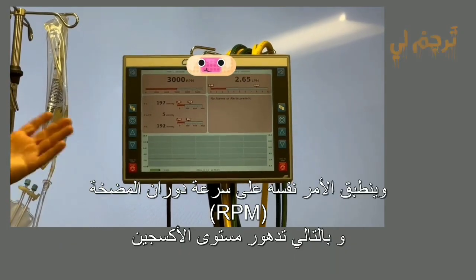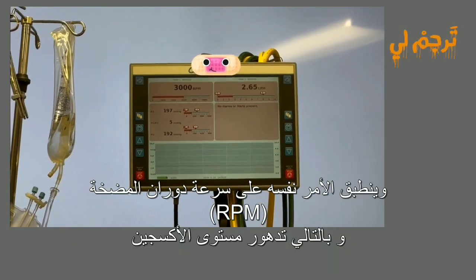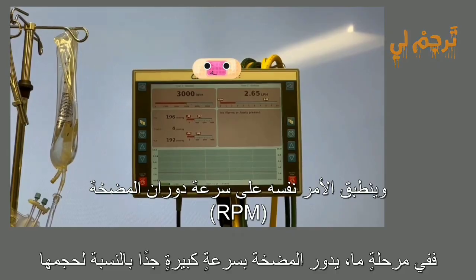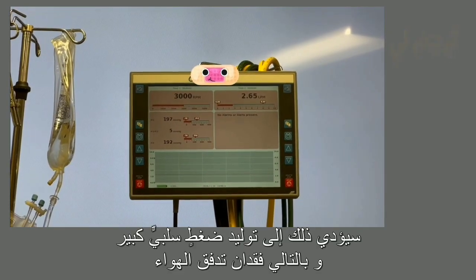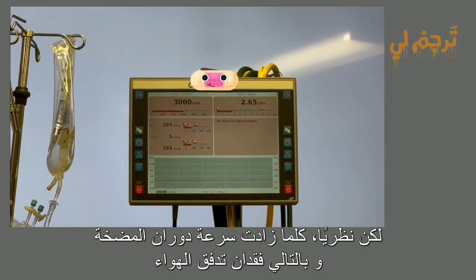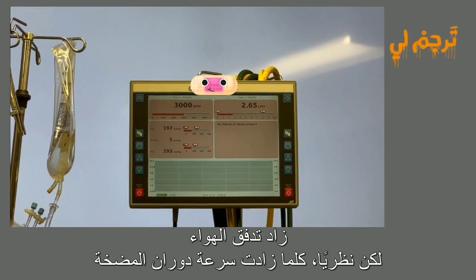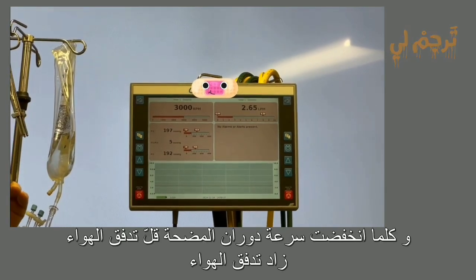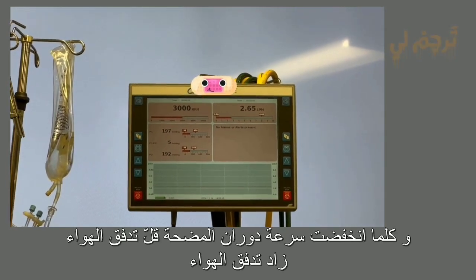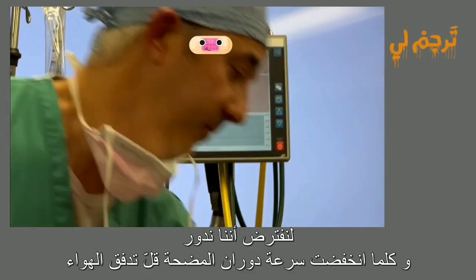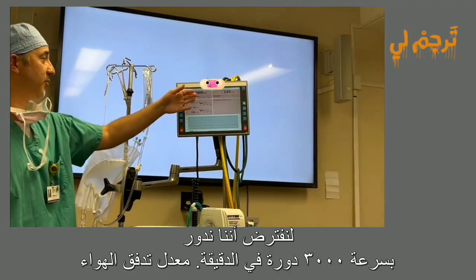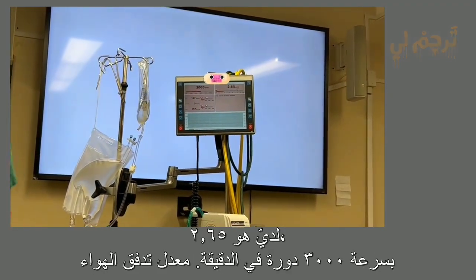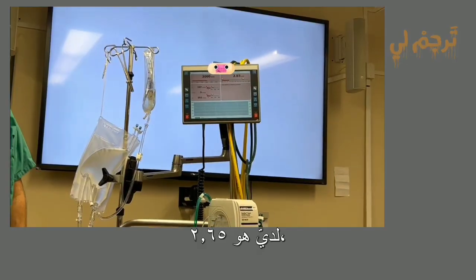Same thing with RPMs. At some point, you're spinning too fast for how much volume you have. You're going to create too much negative pressure, and you're actually going to lose flow. But theoretically, as you go up with RPMs, the more flow you get. Come down in RPMs, the less flow you get. So let's just say we're spinning at 3,000 RPMs.